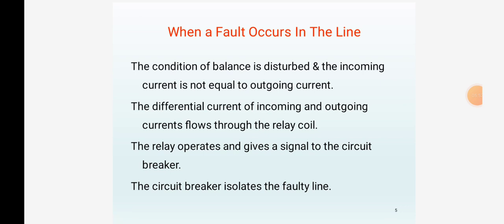When a fault occurs in the line, the condition of balance is disturbed and the incoming current is not equal to outgoing current. The differential current of incoming and outgoing currents flows through the relay coil. The relay operates and gives a signal to the circuit breakers. The circuit breaker isolates the faulty line.